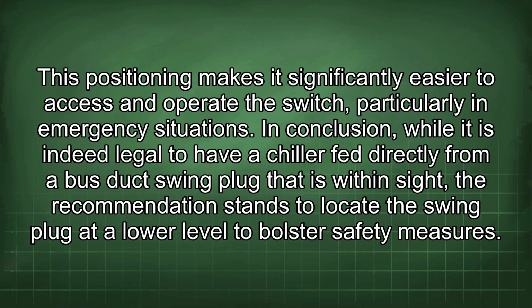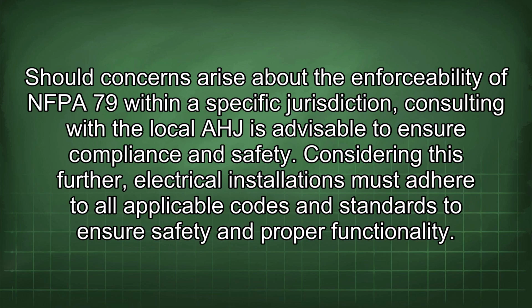In conclusion, while it is indeed legal to have a chiller fed directly from a bus duct swing plug that is within sight, the recommendation stands to locate the swing plug at a lower level to bolster safety measures. Should concerns arise about the enforceability of NFPA 79 within a specific jurisdiction, consulting with the local AHJ is advisable to ensure compliance and safety.